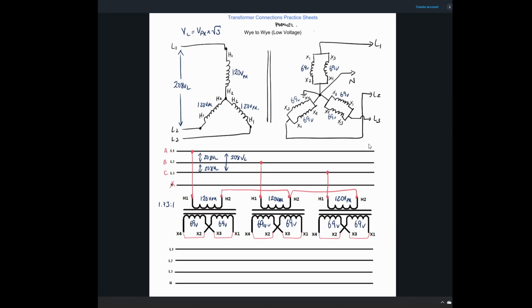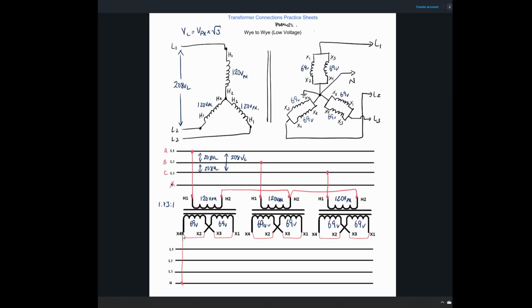Beautiful. This center point here, we are going to bring out to the neutral. So for my first transformer, I am going to bring that guy out to the neutral here. But we need to make sure that all our 2s and 4s are brought to the same potential there. So we'll do that in green here. That is coming out and feeding this guy. Again, you don't have to bond this to ground in the shop because it's not really going to affect your labs or any of the voltage that you see, because we don't have any physical loads connected to here. But normally on a Y, we would have bonded that neutral to ground. Okay, and then we need to bring all of these to the same potential.